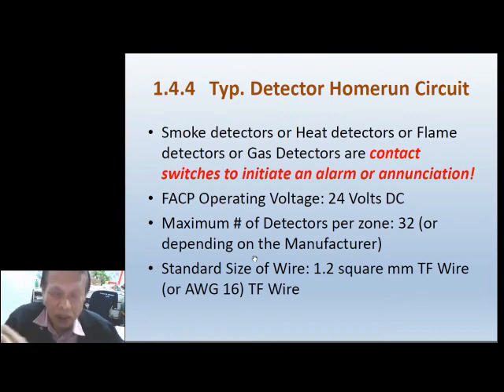Remember, when you design or install an FDAS, you have to make sure your system is just one brand. You can't mix and match. That's different from electrical wiring, where you can buy conduit from one brand, wire from another, circuit breakers from another, switches or outlets from yet another. You can combine different brands there, but in FDAS, you have to get the components from only a single supplier or brand. Only the TF wire and the conduit can differ, but the components - the fire alarm control panel, heat detectors, smoke detectors, manual pull stations, alarm bell, etc. - must all come from the same brand.